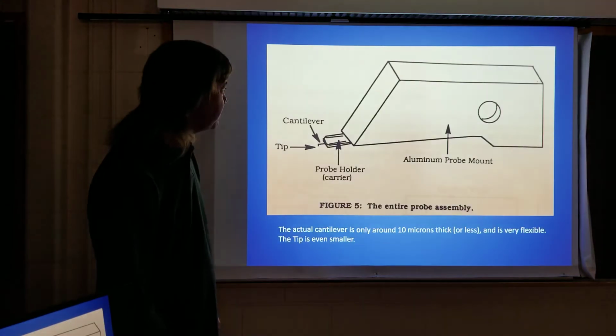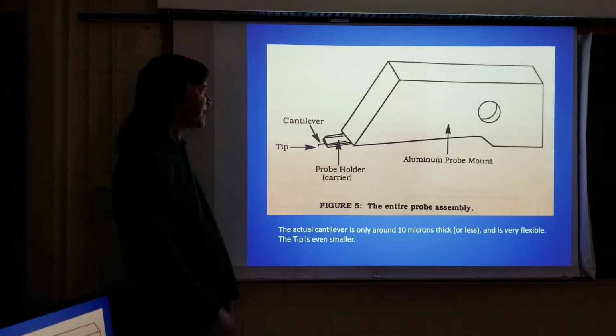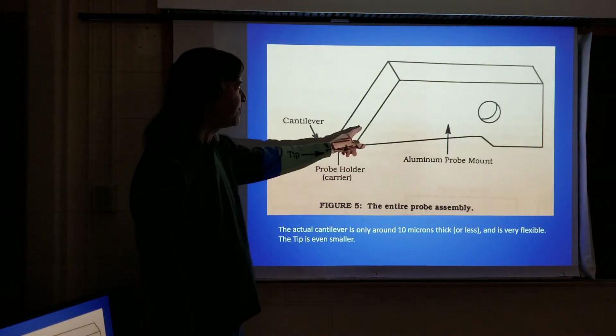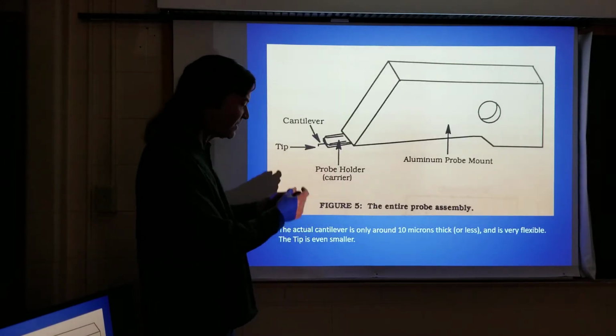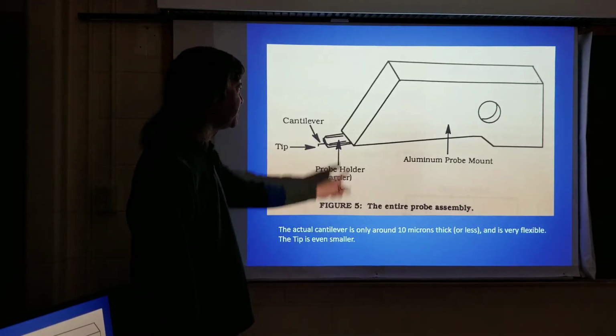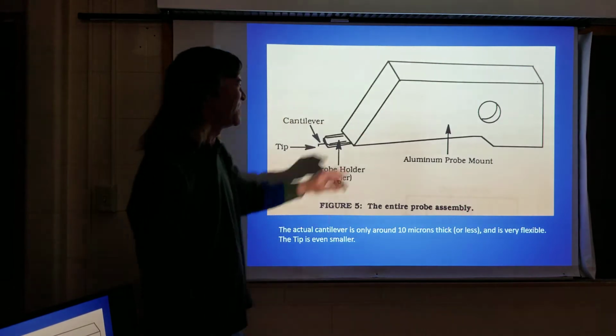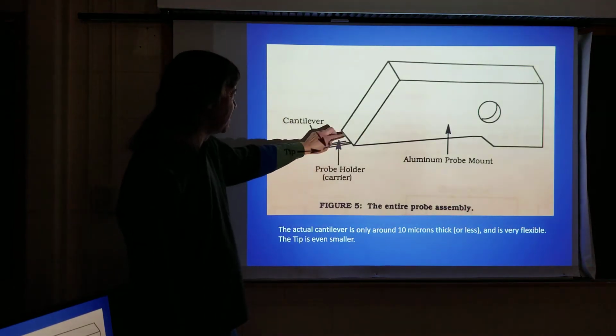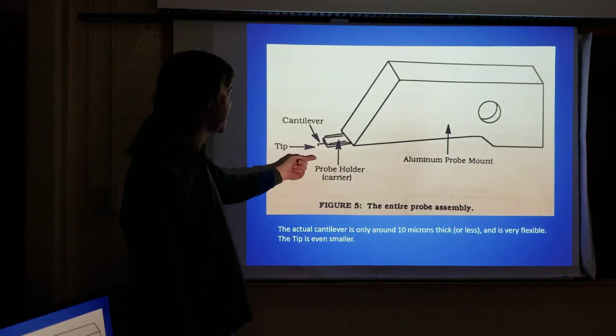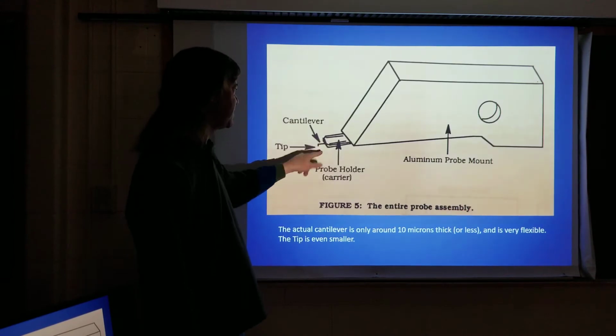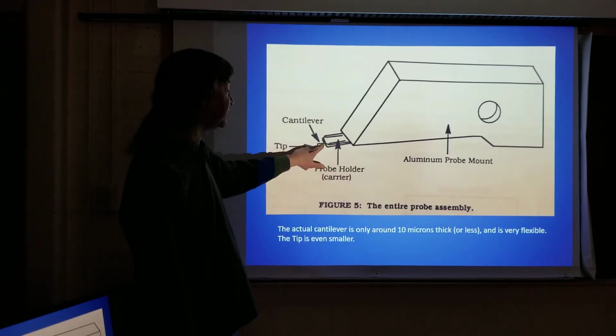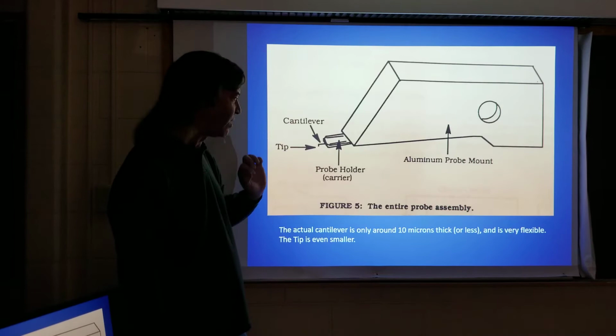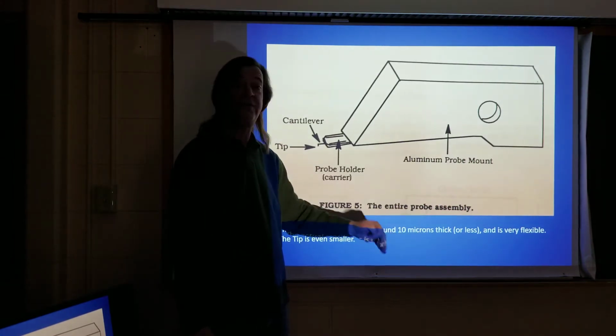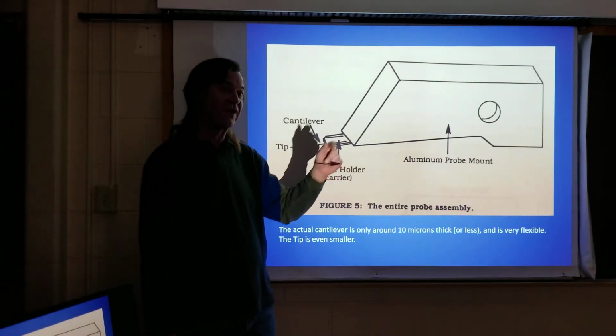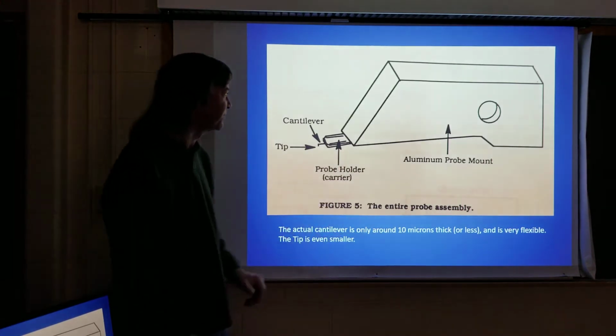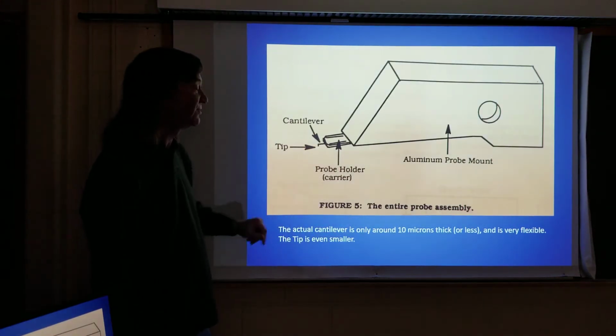Okay. Here's a big blow up of the probe mount. The aluminum probe mount that we use on the AFM I have is maybe three-quarters of an inch across. So it's not, of course, this big. Then we have the actual probe holder, and on that, the tips are attached. So the cantilever is just this little guy right here. They're very small, about 10 microns or thinner. The thinner it is, the more flexibility and accuracy you'll have from the surface. And then the actual tip itself is extremely small.